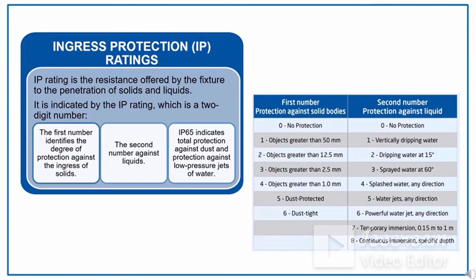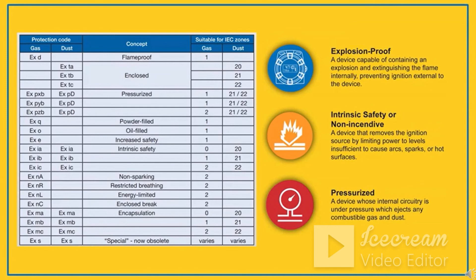Explosion protection classification. Every product will have at least one explosion classification, which is a code indicating the protection concepts and approved environment in which this item can be used. The classification begins with EX, where EX denotes that it has been certified against the international or IEC standards. Where the equipment contains electrical sources, there are a number of ways to prevent spark, heat or short circuits from causing ignition of the explosive atmosphere. One is filling the enclosure with a material which acts as a barrier, which can be a powder, a liquid, a solid or pressurized inert gas. Or else reducing the energy, which means intrinsic safety. The entire classification is also shown in this table.